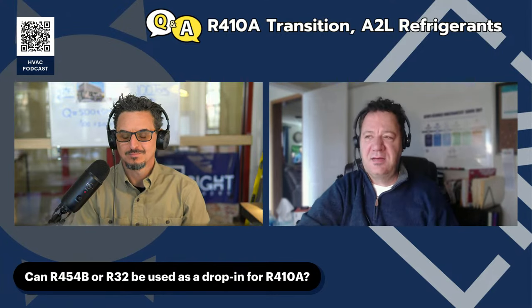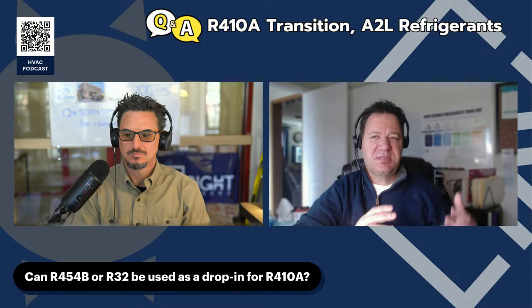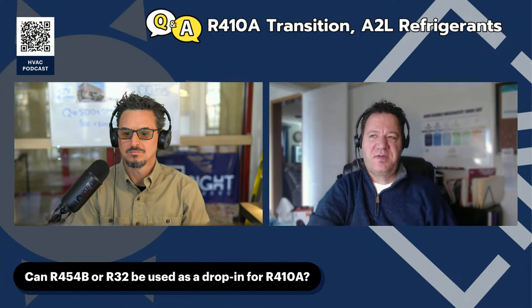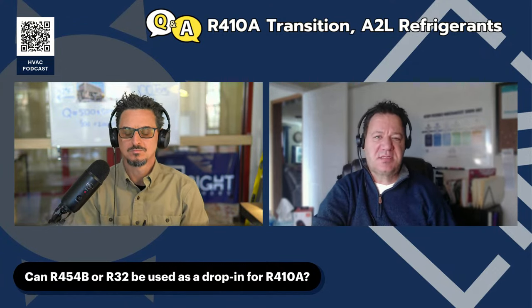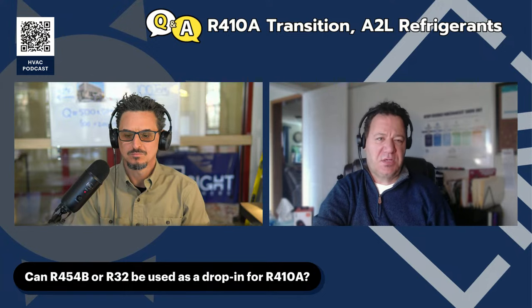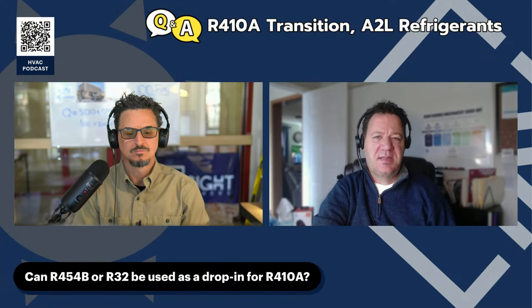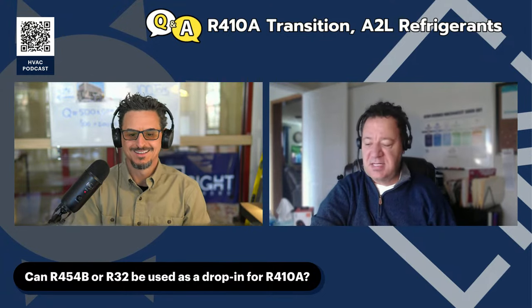Again, going back to that TXV, anytime we change refrigerants, you're going to change that pressure setting on that TXV. So most of the things in the coils, material wise, are going to stay pretty much the same, but there is some changes in that 454B compressor because of that HFO molecule, material wise.